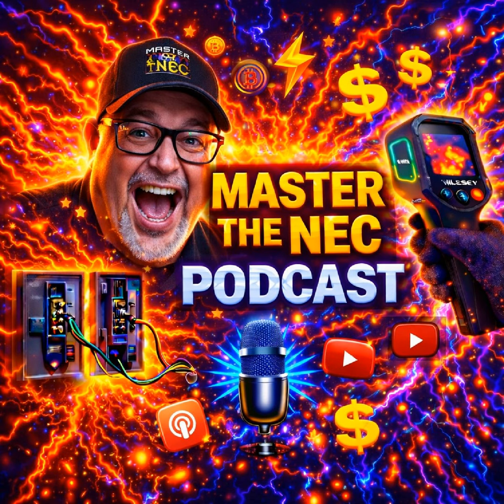Now, conversely, somebody's going to say, well, Paul, I like to use those little transfer switches that do switch the neutral. So how do you deal with that? What changes when we actually switch the neutral? Okay, now let's change this equipment out. We're not going to do an interlock. We're going to put a transfer switch in. So instead of leaving the neutral connected, the transfer equipment actually switches the neutral the same as it switches the ungrounded conductors. Perfect. So when we're on utility power, we've got the normal utility connections. When we transfer to a generator, that line 1 and line 2 from the utility disconnect, and the utility neutral is disconnected from the generator-supplied system. So it's isolated. Everything's switched. Now, the generator grounded conductor is no longer solidly interconnected with the utility supply grounded conductor because it is switched.